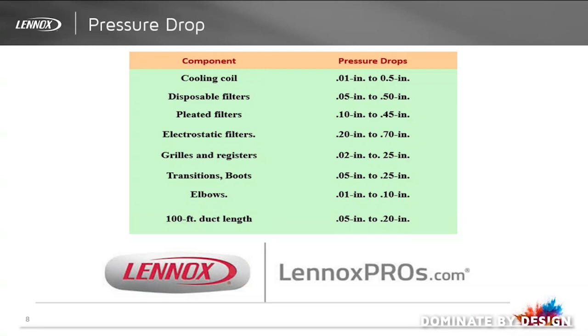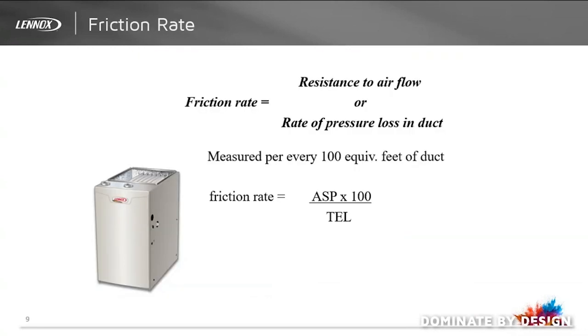If you want to know where to find the pressure drop for various pieces of Lennox equipment, simply go to LennoxPROs.com and search in the document library for the engineering handbooks. It is in these documents where you will find this information. Now we're going to look at the friction rate formula. The actual friction rate equals the available static pressure, or ASP, times 100, divided by the total equivalent length, or TEL.